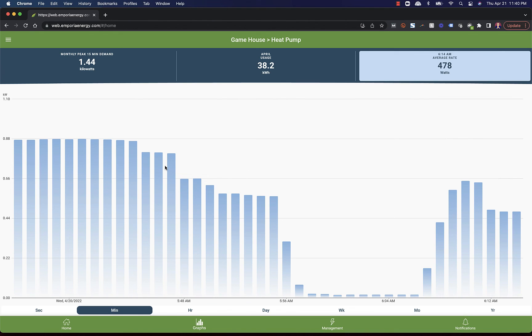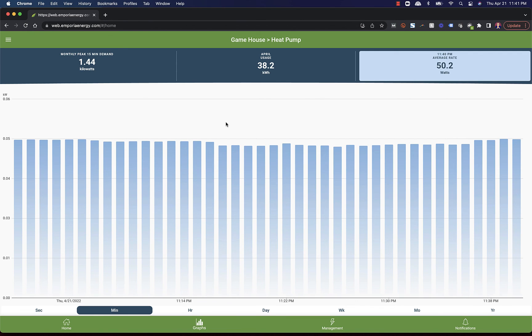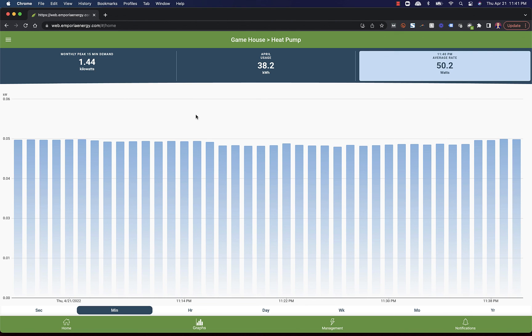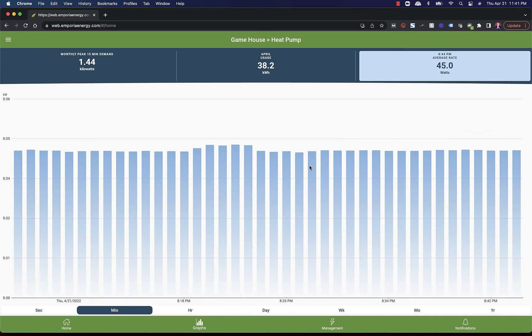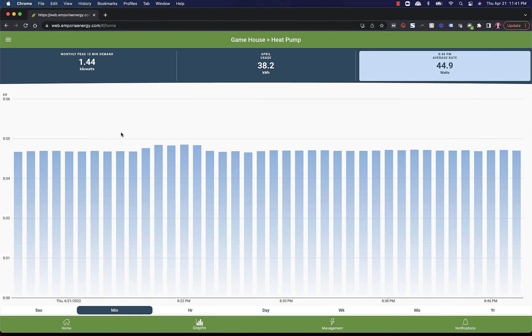And I have to say that the comfort in this house is really, really good. It's better than the one that I'm sitting in here. This is our own house, which has a Bosch heat pump, which tends to freak out. It's like, oh crap, there's load. And it ramps all the way up. And it stays there. And then it shuts off. So it runs at two tons or nothing. I have a dip switch so it can't run at three. It can only run at two. But it tends to freak out and then shut off. And it's really annoying. This system here is doing what you want to see it do. I didn't play with it for a little bit and it kicked back to Thursday. So anyway, I wanted to make this video to show how nice the Daikin Fit is modulating.